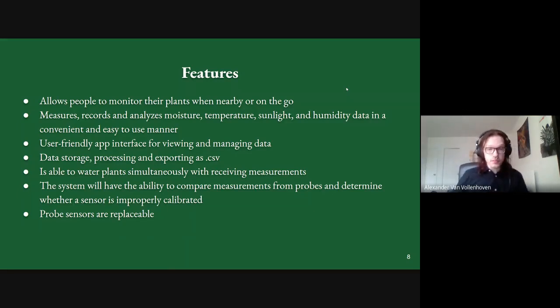Additionally, we want to have it so that the probe itself has multiple sensors for each value, meaning that if one of them, for example, breaks or produces for any reason an inaccurate measurement, the probe itself will realize that because it no longer matches the rest of the measurements. And it will then tell the user that a certain sensor needs to be replaced, which the user can then easily do.